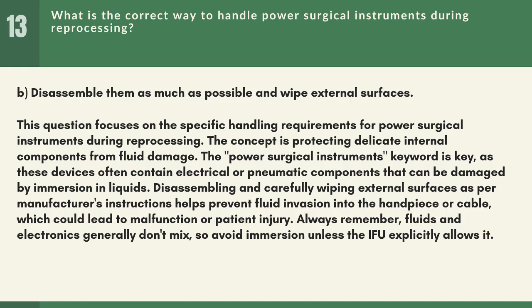This question focuses on the specific handling requirements for power surgical instruments during reprocessing. The concept is protecting delicate internal components from fluid damage. The power surgical instruments keyword is key, as these devices often contain electrical or pneumatic components that can be damaged by immersion in liquids. Disassembling and carefully wiping external surfaces as per manufacturer's instructions helps prevent fluid invasion into the handpiece or cable, which could lead to malfunction or patient injury. Always remember, fluids and electronics generally don't mix, so avoid immersion unless the IFU explicitly allows it.